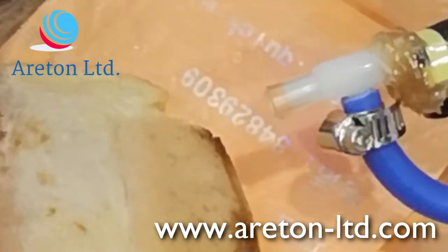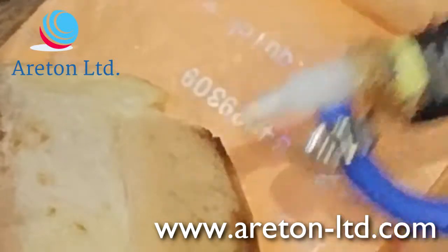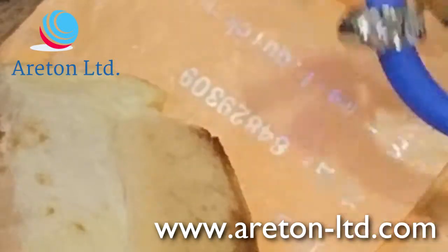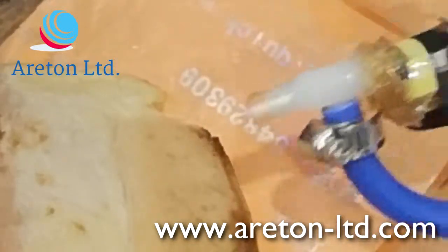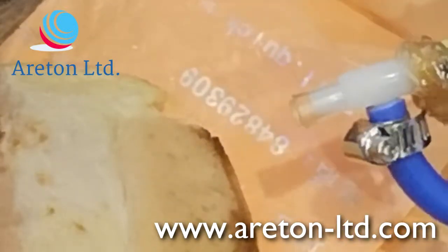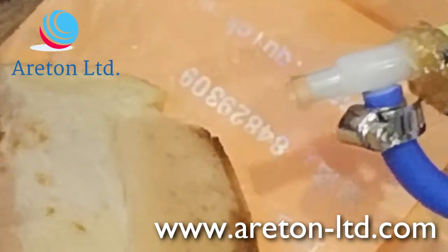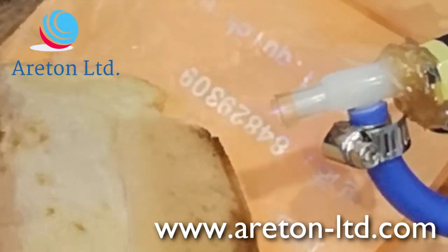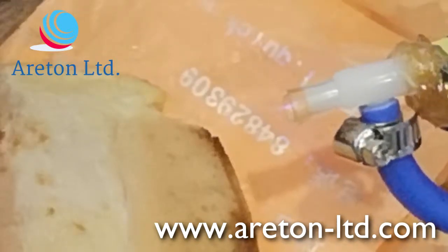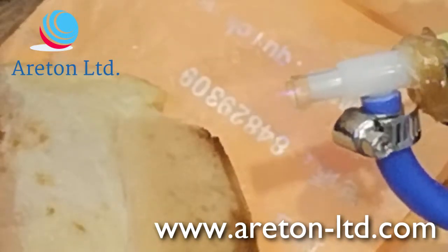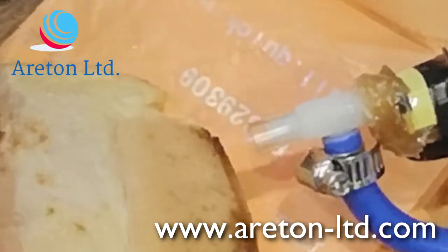I'm going to do it again, and it's off. I'm going to do it again, and it's off. Because it's actually counting the overall 900 milliseconds time. So when you hear it beeping, it's actually detecting the arc. I'm going to do it again.